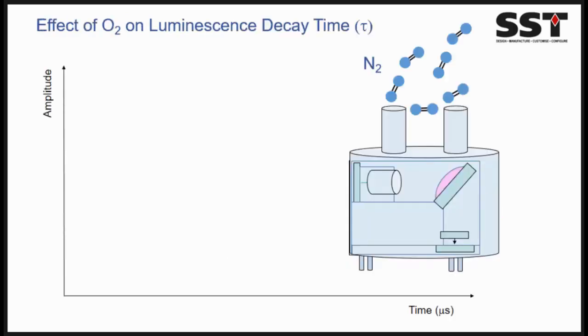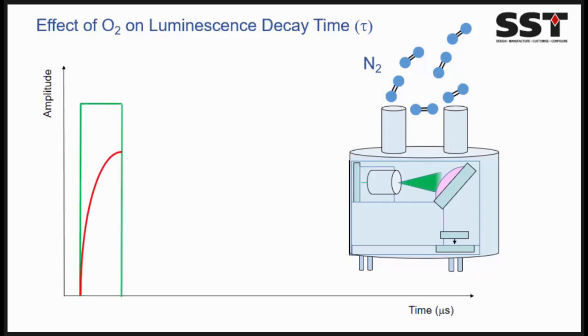So in an oxygen-free environment, in this case I've just used nitrogen as an example, the LED will pulse and hit the oxygen sensing layer, and we will get a luminescence signal that will pass to the photodiode. So here, this is the LED on time, and this is the rise from the luminescence, and we collect what we call the decay time. You can measure either luminescence intensity or luminescence decay time. We chose luminescence decay time for various reasons. Number one being that intensity-based sensors are so sensitive to changes in, for example, the output power of an LED. If that changes, the intensity will change. And in the most standard way, you will get intensity changes from the formulation here. When you do decay time, you take out these aspects. So basically we monitor the decay every second.